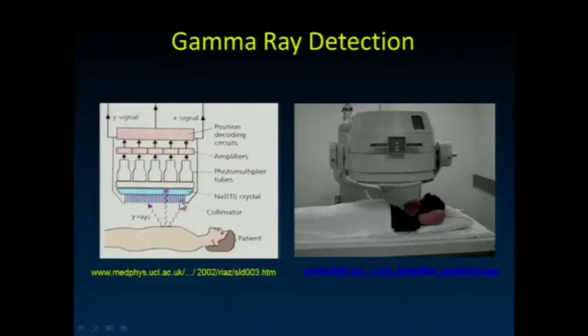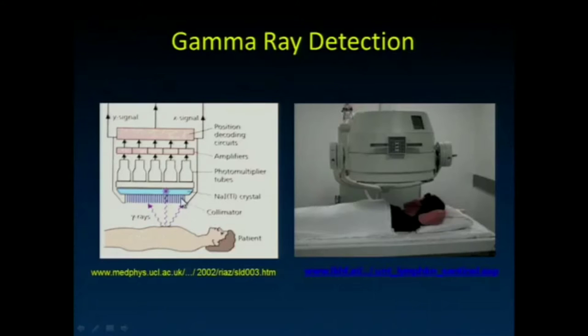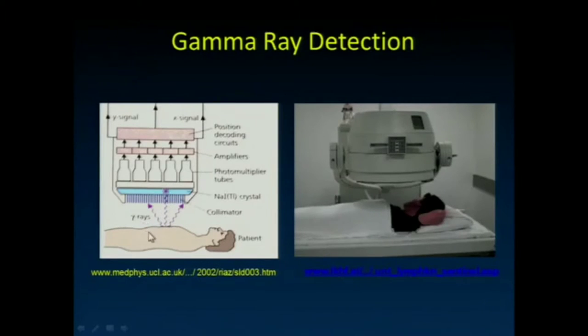Here's the gamma camera. On the front we have the collimator, analogous to the grid. In radiographic imaging, we use a point source of radiation from the x-ray tube, so the image is in focus. But when we give a radiopharmaceutical to a patient, we end up with a distributed source of radiation. So we need to ensure we only detect gamma rays traveling in a particular direction, otherwise the image is just an absolute blur of activity traveling in all different directions.